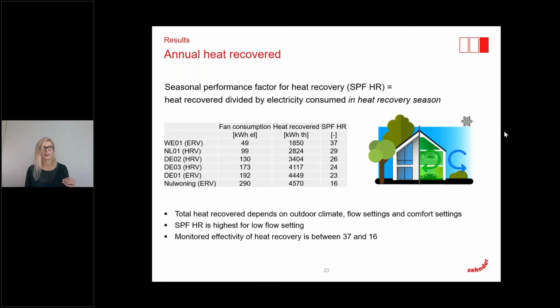In those 6 real cases where we have measured real results, the results are in the tables, and we have a seasonal performance factor for heat recovery, SPF-HR, from 16 to 37. Usually for heat pumps, this is around 4 or 3 in good cases. If we have a higher number, that means the work that is required is less, and therefore the costs are less. So to answer Adrian, this consumption of electricity is rather a marginal amount in comparison to the recovered energy.